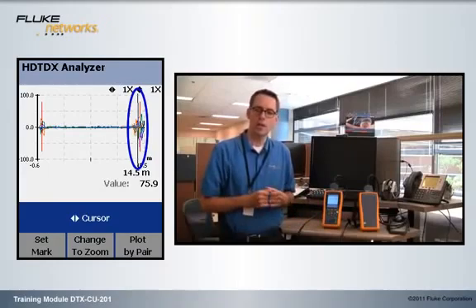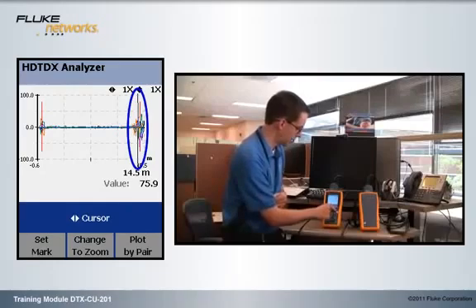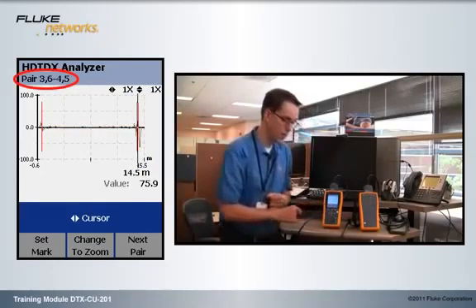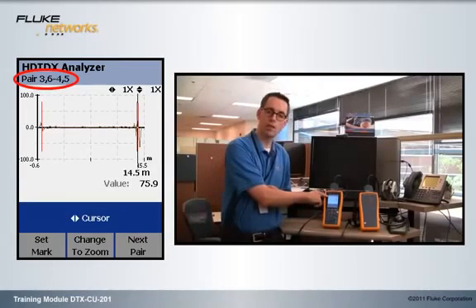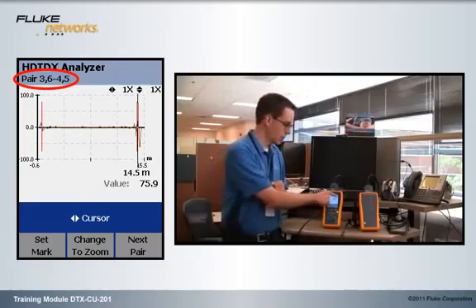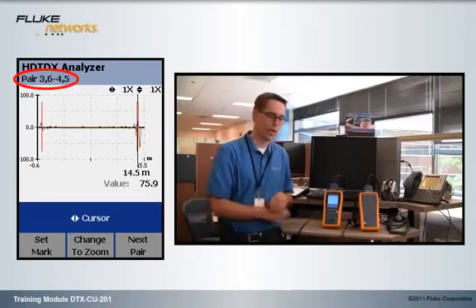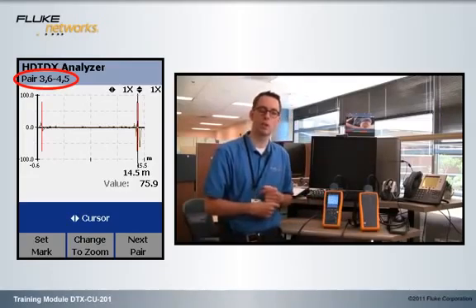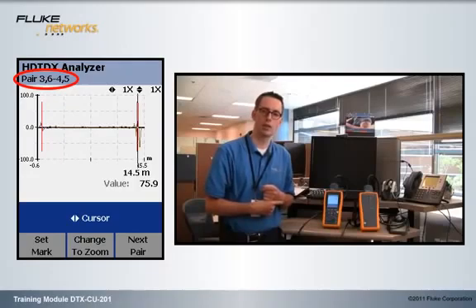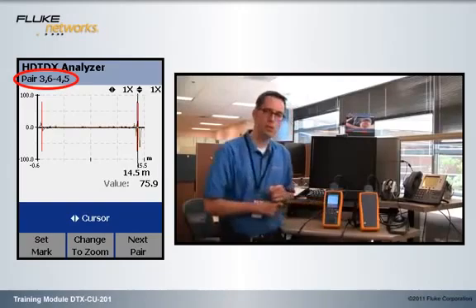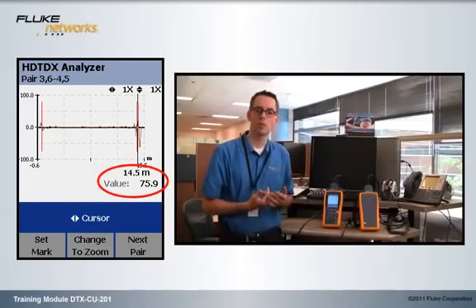We're only interested in that pair combination that failed, which is 3645. So I'm going to press the F3 key until I get to 3645 in the top left-hand corner there. Now the cursor has automatically gone to the largest source of crosstalk, which happens to be right over the red line at the remote end, suggesting that we have an issue in our connection at the far end of the link. Below it, you'll see a value of 75.9. That's a percentage value. Is it good or is it bad?